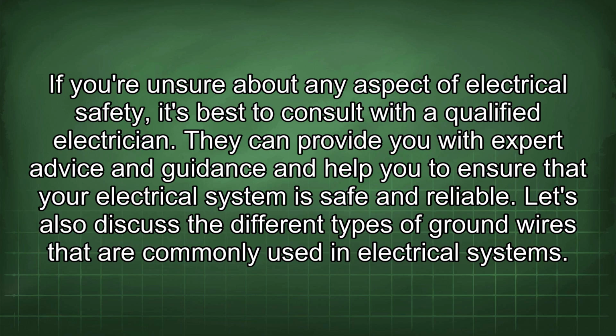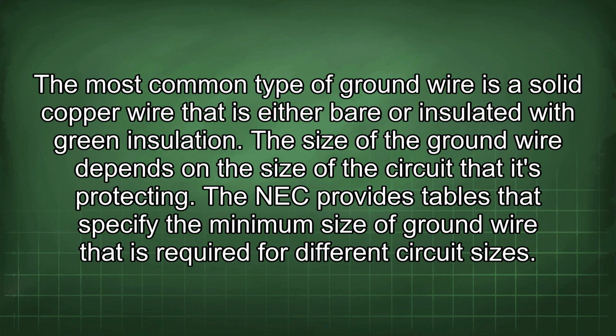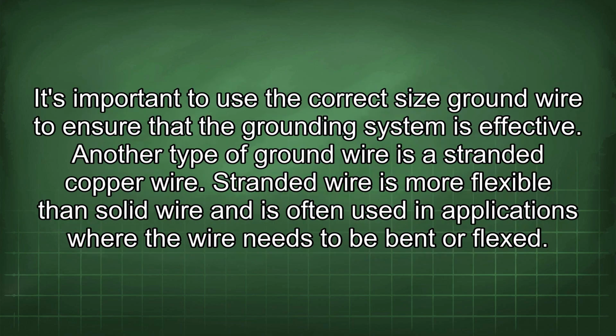Let's also discuss the different types of ground wires that are commonly used in electrical systems. The most common type of ground wire is a solid copper wire that is either bare or insulated with green insulation. The size of the ground wire depends on the size of the circuit that it's protecting. The NEC provides tables that specify the minimum size of ground wire that is required for different circuit sizes. It's important to use the correct size ground wire to ensure that the grounding system is effective.